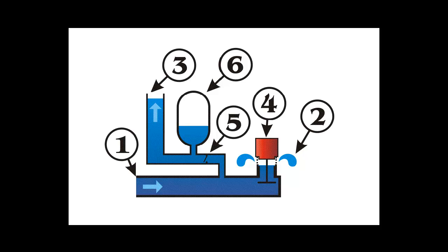Meanwhile, the water hammer from the closing of the waste valve also produces a pressure pulse which propagates back up the supply pipe to the source where it converts to a suction pulse that propagates back down the pipe. This suction pulse, with the weight or spring on the valve, pulls the waste valve back open and allows the process to begin again.